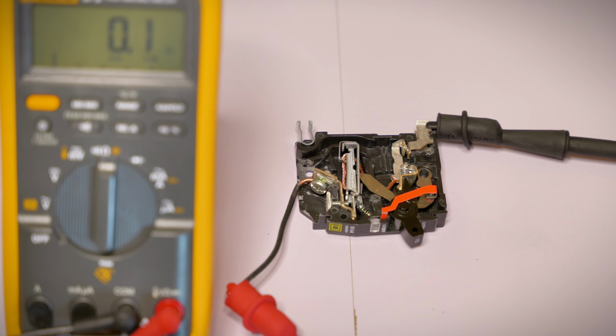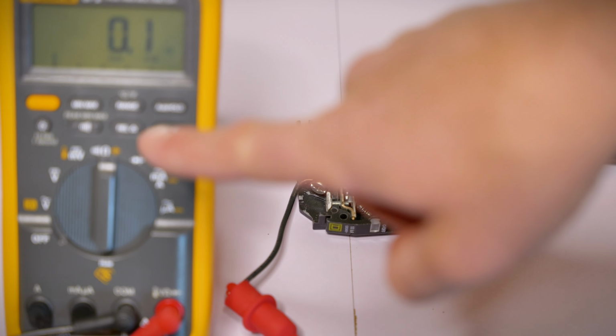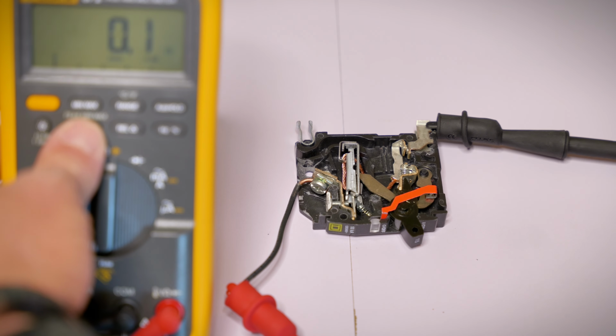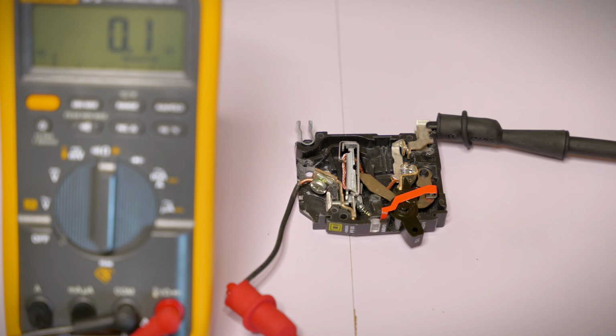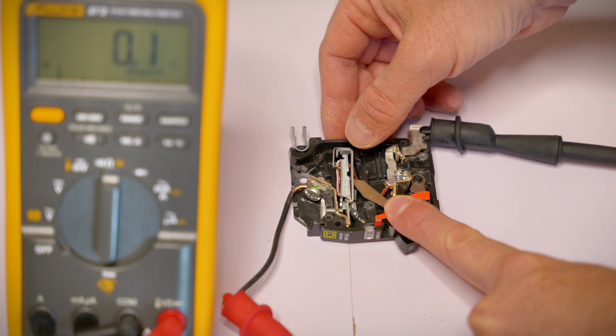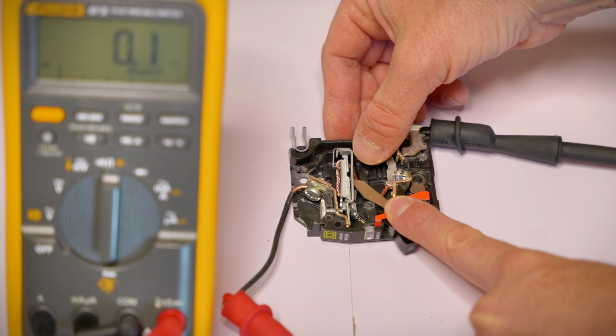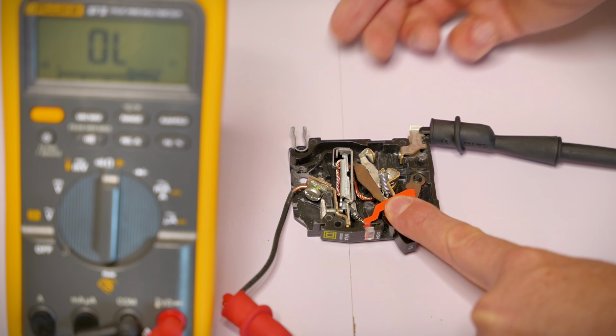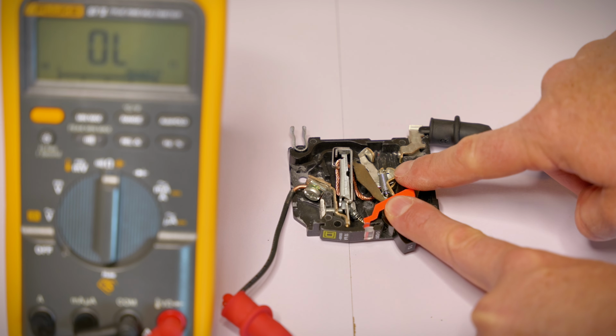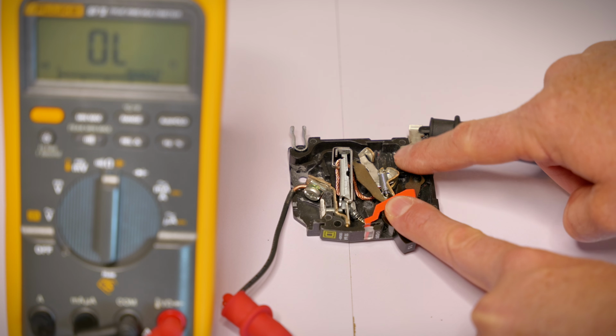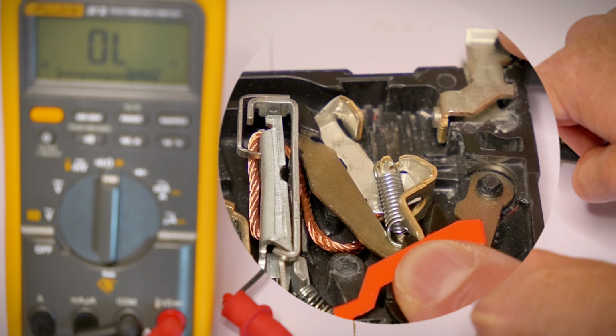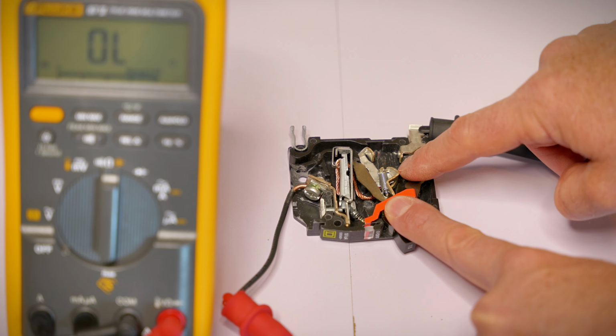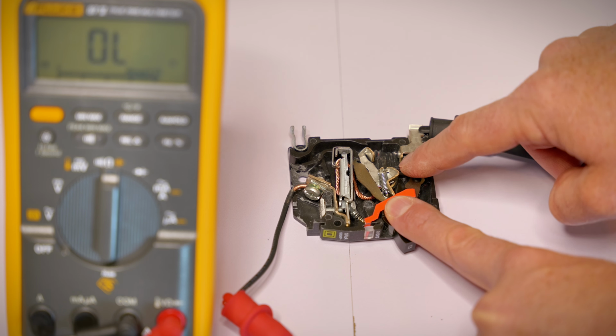Now we'll do a quick demonstration. I've set up my meter in series with this. I've got it in the continuity setting, so we'll go ahead and turn that on. You can hear that the circuit is being made. When you have a heat up condition, this thermocouple is going to move over and trip. Now, if you notice, the moving lever there inside has broken away from the non-moving terminal, and this is actually what interrupts your circuit right here.